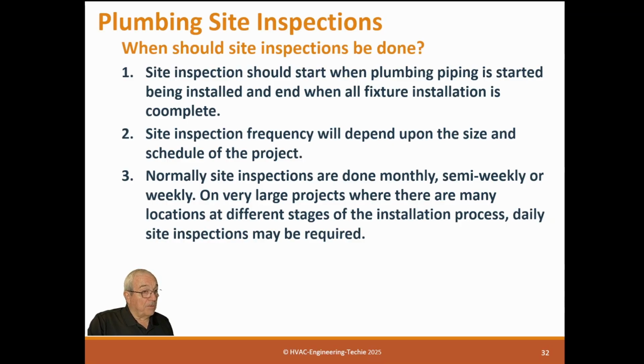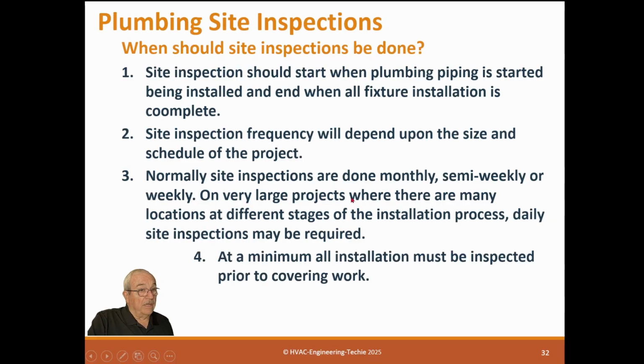That means you would have a person on site full time. I've never actually had a job that way. Even though I've had some very, very large jobs, we've always been able to do them on a monthly basis or a semi-weekly basis. So we may have an inspection monthly, but we have test schedules at other times. And so basically you have that at different times. At a minimum, installation must be inspected prior to covering work. So you can't allow any work to be covered unless it's been inspected.